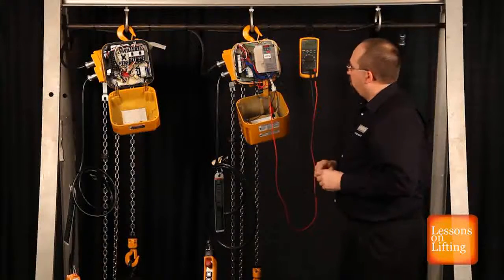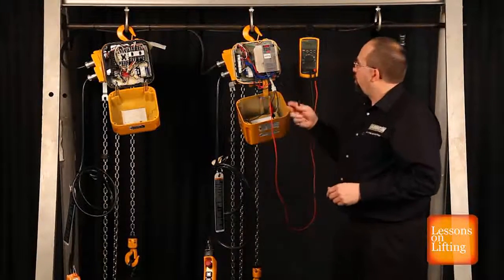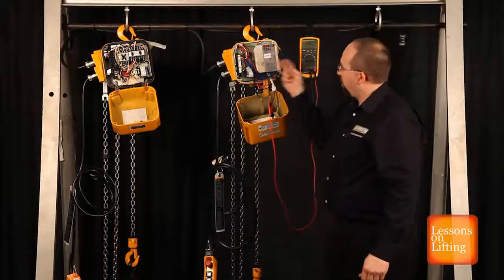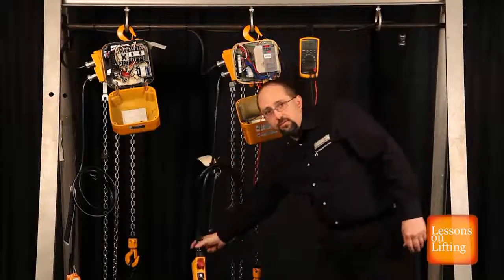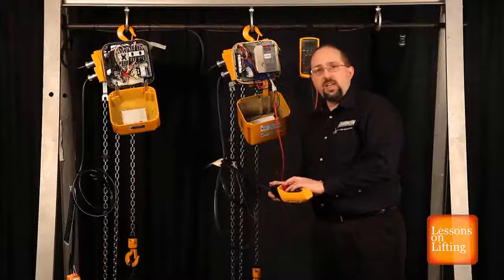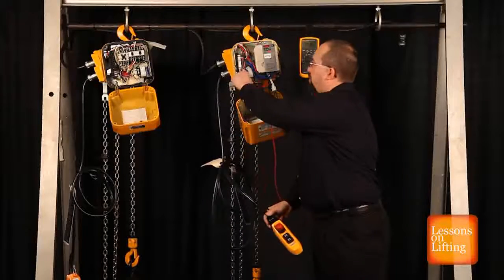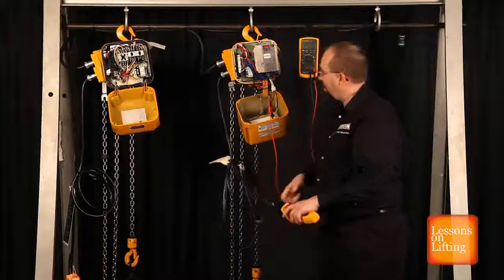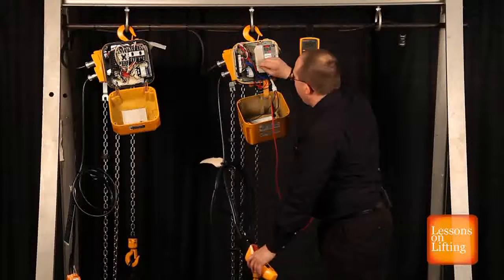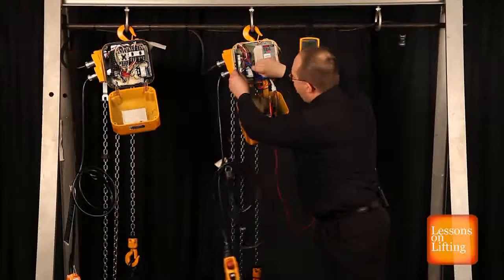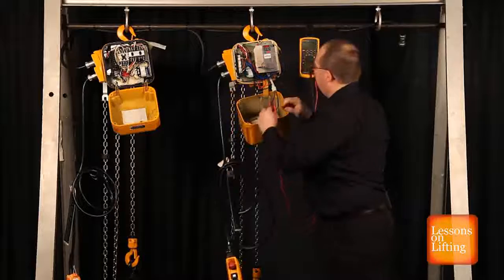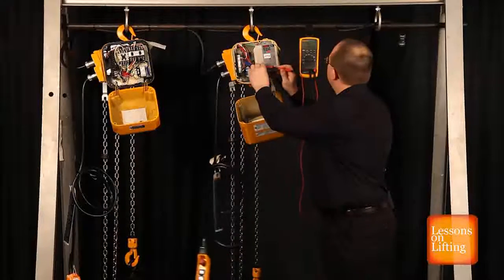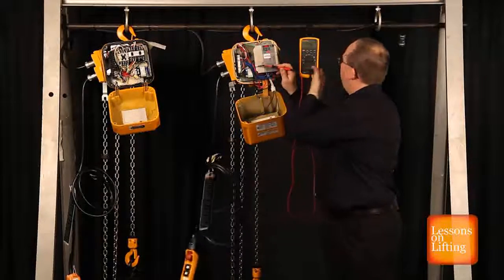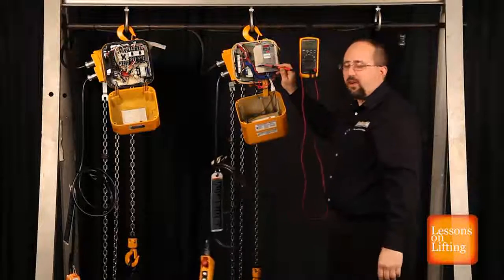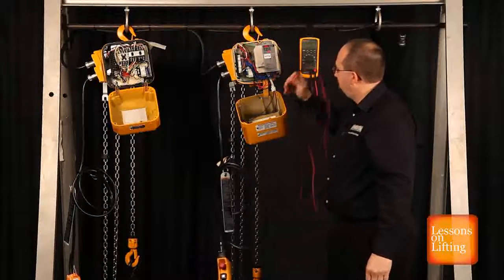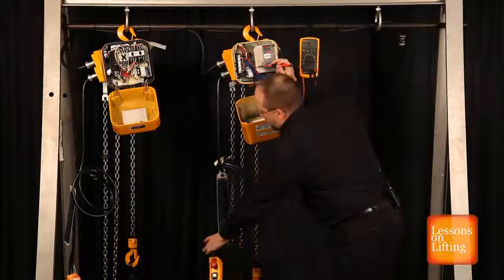Since we had control voltage there, we know from the wiring diagram it leaves pin 4 here, goes down to the pendant, through the E-stop, comes back up to pin 5. All right, so we're going to check and make sure we have control voltage on pin 5. That will verify that whole part of the circuit. Pin 5, we have 125 volts. That's good. We know that the circuit's working.